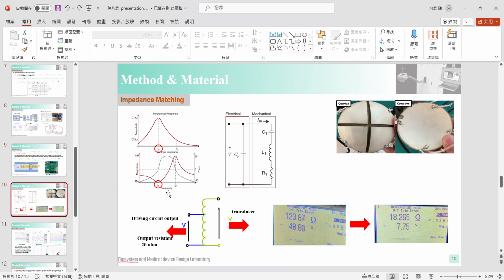In our matching unit, we have incorporated a self-impedance transformer connected in parallel with the transducer. Our transducer uses piezoelectric ceramics, which can be examined from both a mechanical and electrical response perspective. In the figure, Fs represents the resonance frequency, while Fp represents the anti-resonance frequency. On the right side, we have the equivalent circuit of an ultrasound transducer. The transducer exhibits maximum vibration at the resonant frequency.